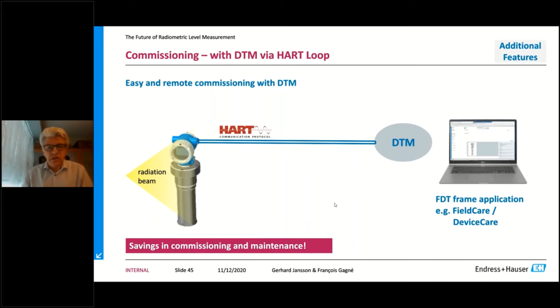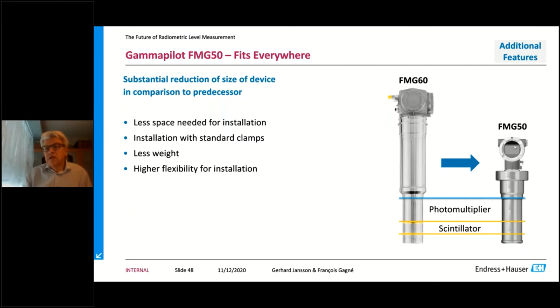Other things we also look at when installing: how heavy is it, can I reduce the weight? With today's technology, you can reduce the weight and reduce the component size. As you see here, this is the old detector, this is the new detector. I think we've reduced the weight by roughly 50%, because this is stainless steel tubing here and stainless steel head there. This is of course easier to install, plus now we have the 4-20 milliampere loop-powered instrument, which makes it even easier. Less weight usually means easier to install. Otherwise the active area would be a similar height, but we have a photo multiplier that is built electronically in a different way.